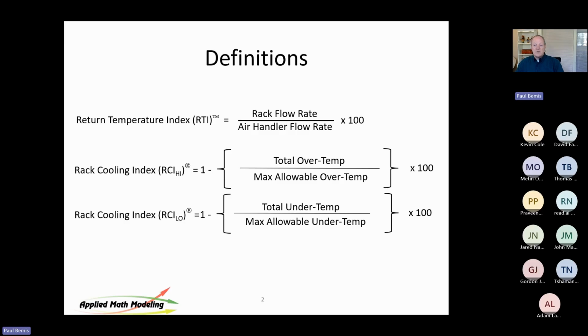And now you have asymmetries because you've got servers running at much higher CFM than 125. I gave you a number of 125, but when those things ramp up, they'll double that. And now I've got servers on one side of my room that are pulling a lot more air than on the other side because I have a hotspot, I've got asymmetry. That's a problem. So you generally want them to run in the ASHRAE recommended range. Not everybody does that. I do have customers running in the allowable instead of recommended, which goes up to 90 on the inlets. But most people try to run in the recommended range. Okay.